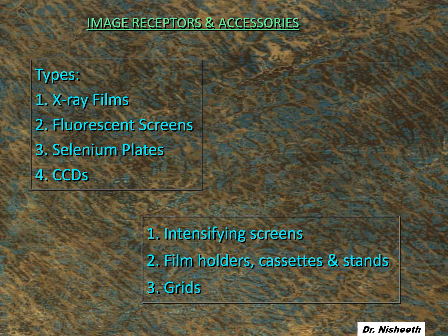Grids basically help remove unsharpness of the image by removing secondary radiation. See, the function of the intensifying screen is to reduce the radiation exposure by converting an X-ray photon into multiple light photons. The disadvantage of the intensifying screen is unsharpness and poor resolution of the image, but the advantage is that the radiation exposure required is reduced.